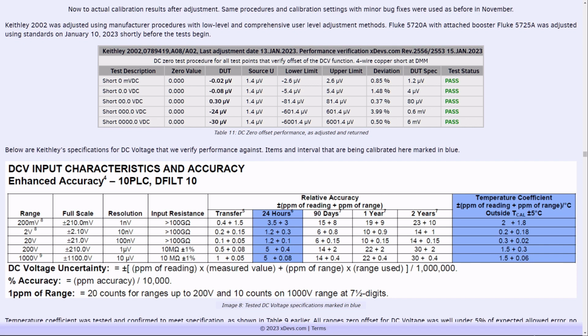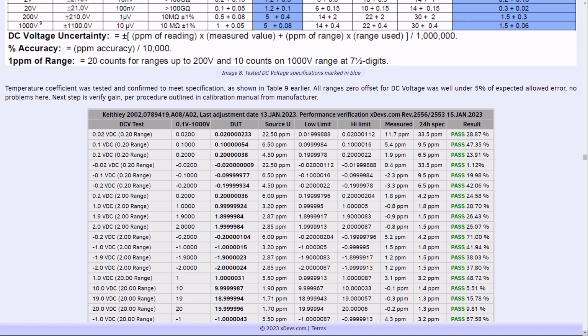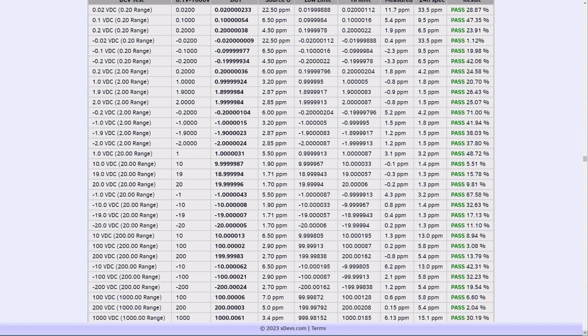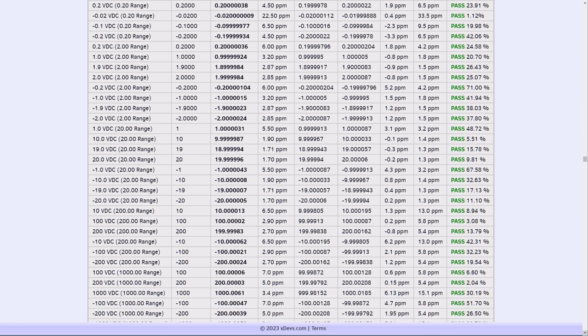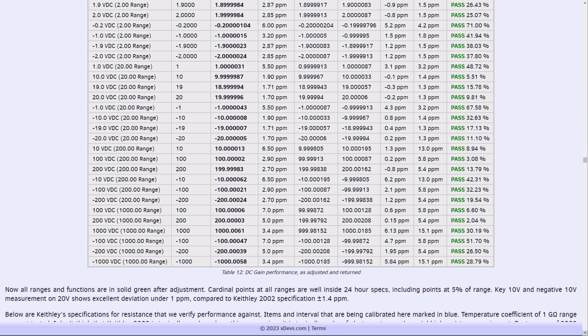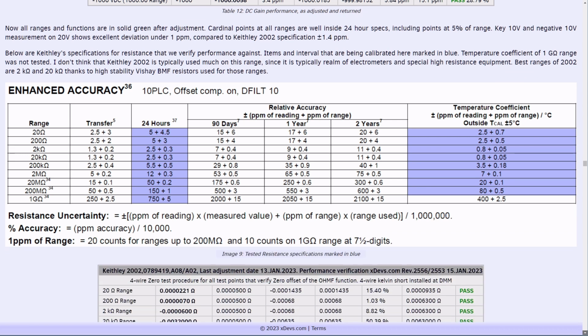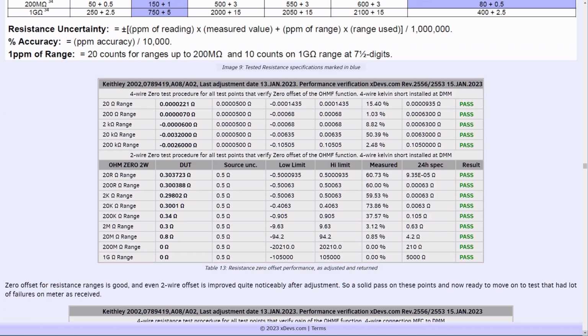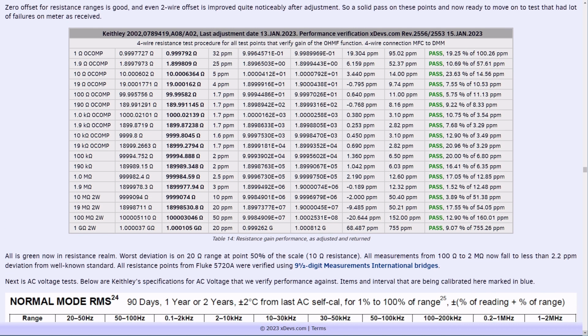Now that adjustment is completed, we can repeat the same calibration performance verification tests and go through all the functions and ranges to make sure everything is good and happy. And we should expect to meet 24-hour specifications with good margins. Because we used a freshly characterized calibrator, there should be no problems to meet specifications within 24-hour specs of Keithley 2002. And indeed we can see all good solid green points for DC voltage function. I've shown additional snapshots from specifications with the tested points marked in blue, just for a better indication.